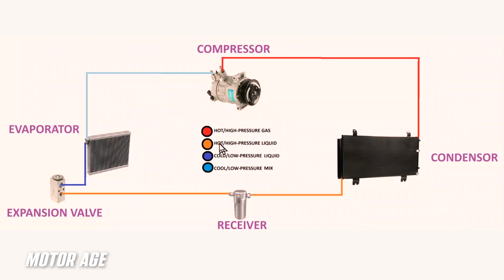Particularly on an expansion valve system like this, where refrigerant is throttled. It's not only metered here across an internal restriction, but it's throttled, meaning we can open up the throttle of the expansion valve and let more liquid refrigerant flow through the evaporator. Or we can close this and throttle down the circulation of refrigerant and reduce the amount of flow through the evaporator.